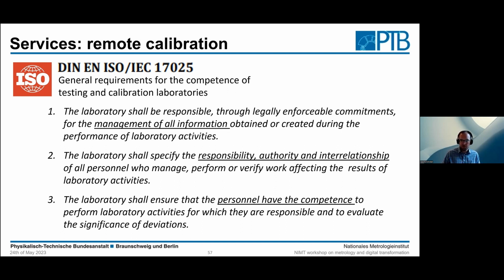So if you have a remote calibration service, it's not sufficient to just have access to the data source of your customers. The laboratory should also specify responsibility, authority, and interrelationship of the personnel carrying out the calibration. So if you do remote calibration, that may mean you have a software in place that does some of the parts, and you have to have responsibility, authority, and interrelationship of that software, because it's then kind of personnel you have to manage. Or you have people from the customer in place that have to do certain steps, and you're also, as a lab, responsible for them, including, and that's the third point I want to mention here from the ISO 17025, the lab shall ensure that the personnel have the competence to carry out the calibration.